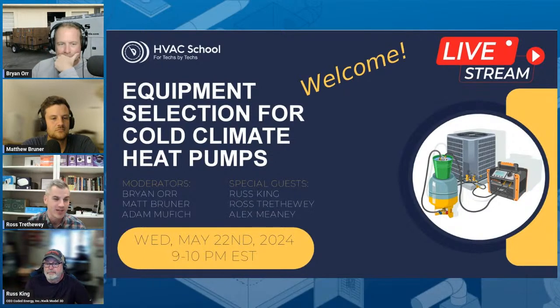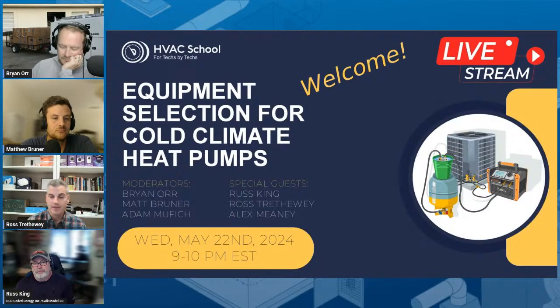The HVAC contractors not making returning phone calls, and so there's challenges there for sure. And so we're in a perfect climate for heat pumps that in the New England market, it's a very tough market to actually get right with heat pumps. We've got heating loads that are 2 times our cooling loads in many houses, and on top of that, we also have really low ambient conditions. If you're talking about Maine, you're talking about negative temperatures. And in Massachusetts, we're in single digits for design criteria. So heat pumps obviously struggle as the temperatures get colder out. So you just got to take that into account.